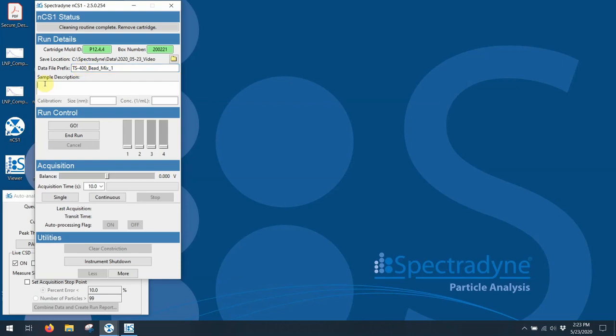In the sample description field, I can put in any kind of metadata I want to that gets carried with all these files. In this case, what I'm going to do is I'm just going to indicate that this happens to be 94, 150, and 208 nanometer traceable beads. And another thing I could do here is I could also put in any sort of dilution or any types of metadata here. Basically, you can type in whatever you want.